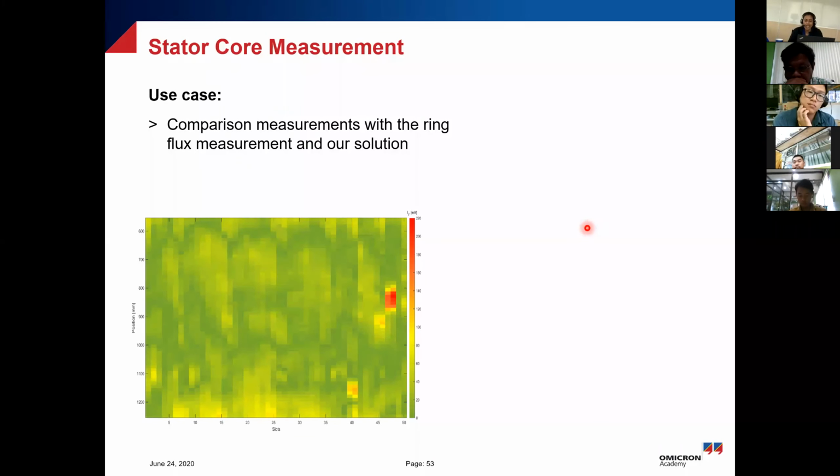In my experience, not a lot. Mostly what I found was that the aging period was the most common cause of failure. Maybe a few, and that's very much related to the manufacturer itself. One particular manufacturer had a higher infant mortality rate. I don't want to name it, but that was the case. But I haven't seen it over the whole range having a very high infant mortality rate, because mica insulation is pretty good in that scenario.